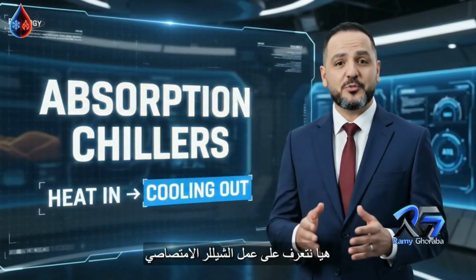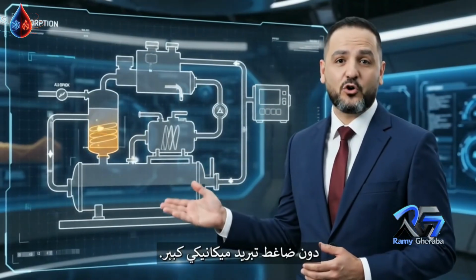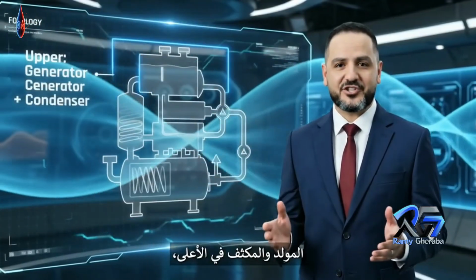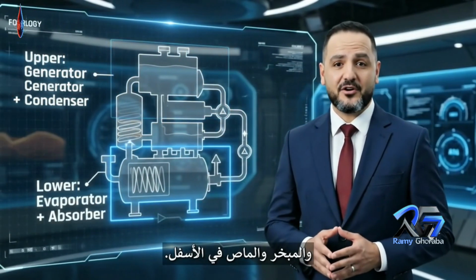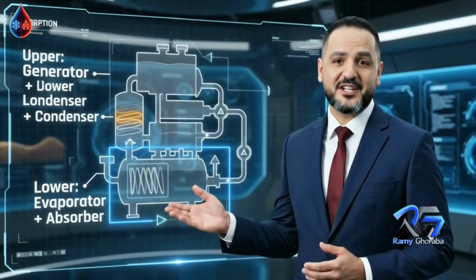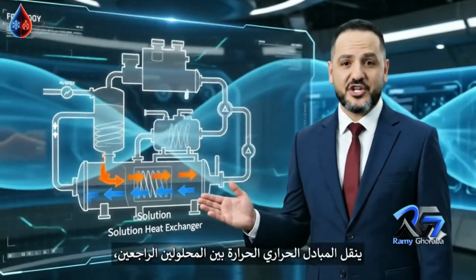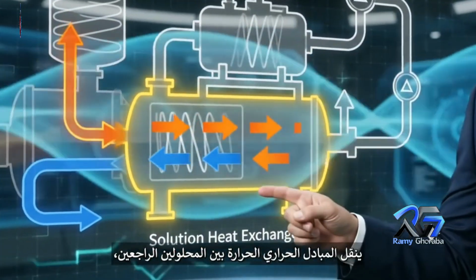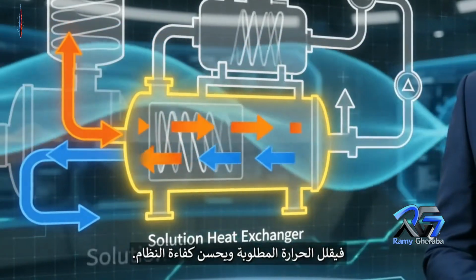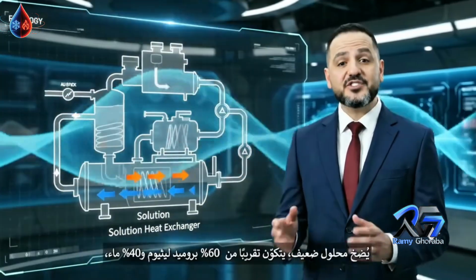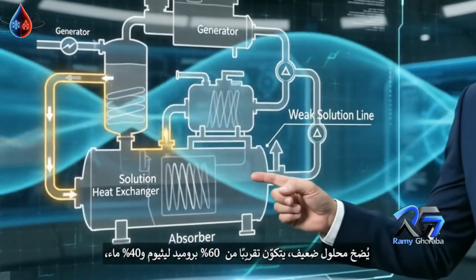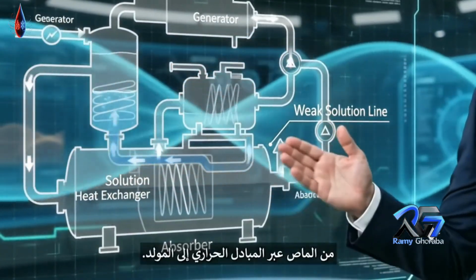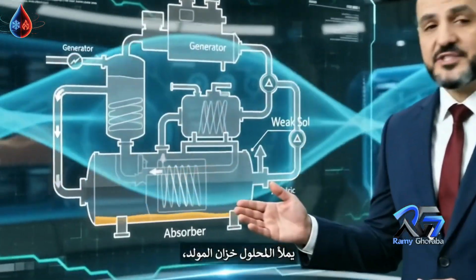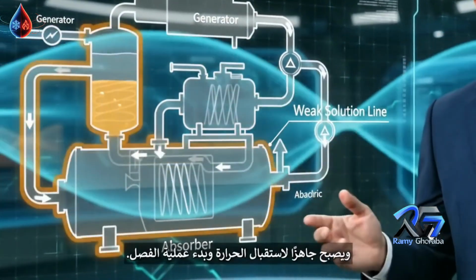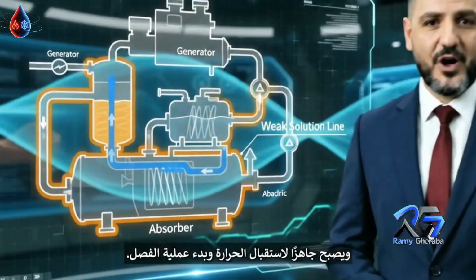Let's discover how an absorption chiller works without a large mechanical refrigerant compressor. The chiller has two main sections. The upper section contains the generator and condenser, while the lower section contains the evaporator and absorber. The heat exchanger transfers heat between the returning solutions, reducing the required heat input and improving system efficiency. Weak solution is pumped from the absorber through the heat exchanger to the generator. It is approximately 60% lithium bromide and 40% water. The weak solution fills the generator reservoir, where it becomes ready to receive heat and begin the separation process.